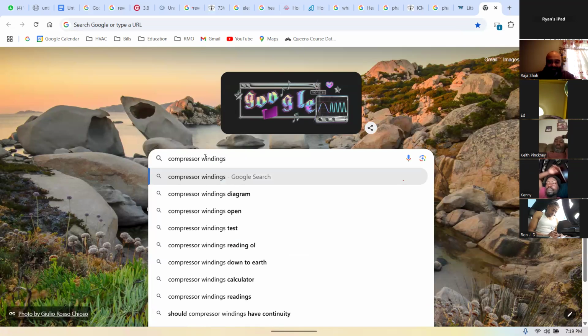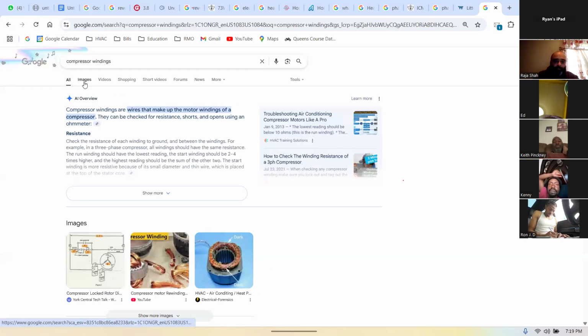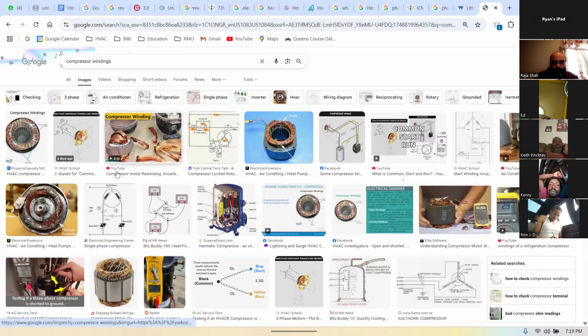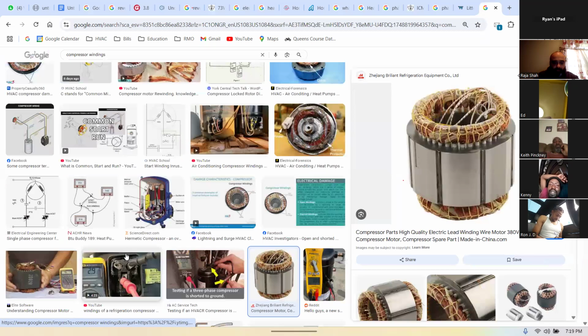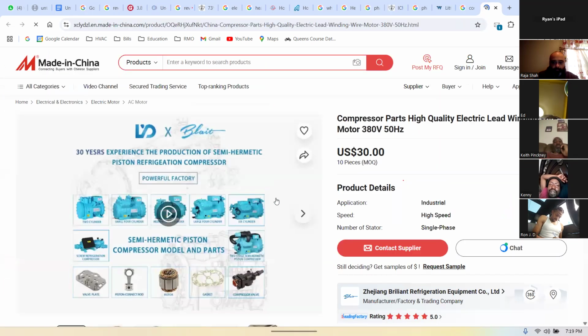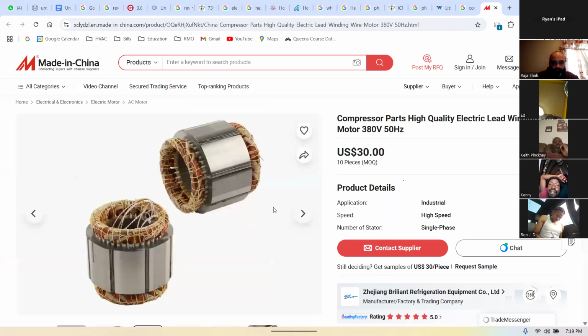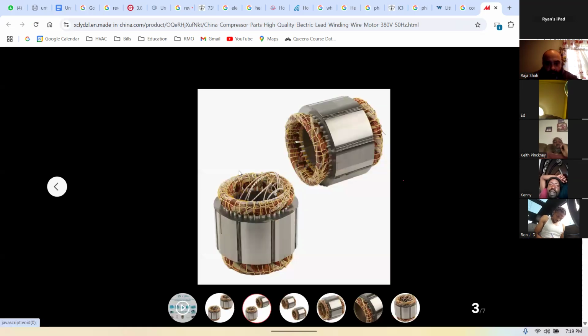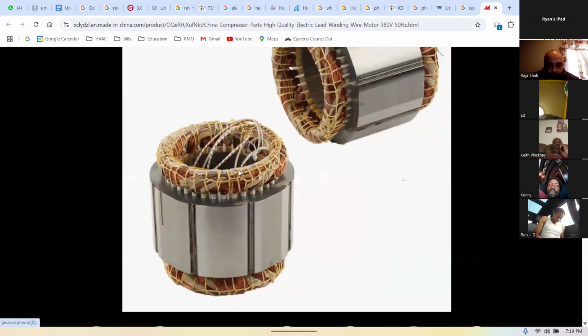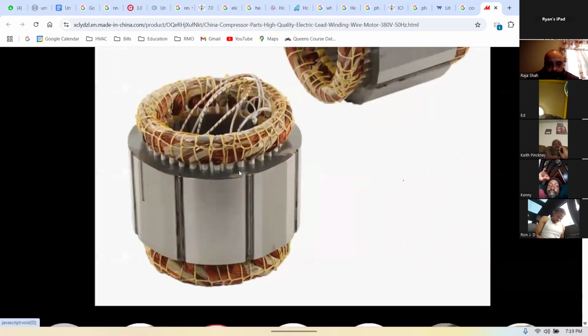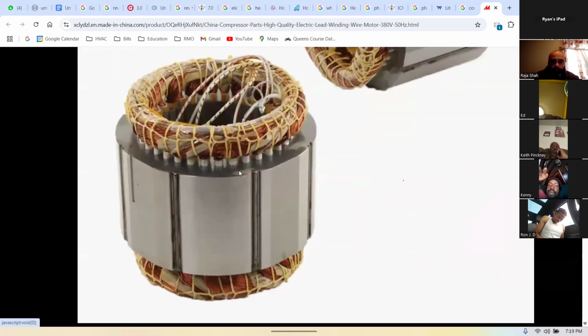The compressor windings itself is insulated. So if it gets too hot, you're going to have a burnout or shortage on the windings, because the insulation basically starts to overheat and it diminishes. Then you will have an open winding on the compressor, and once that happens, your compressor is practically dead on one of the windings.